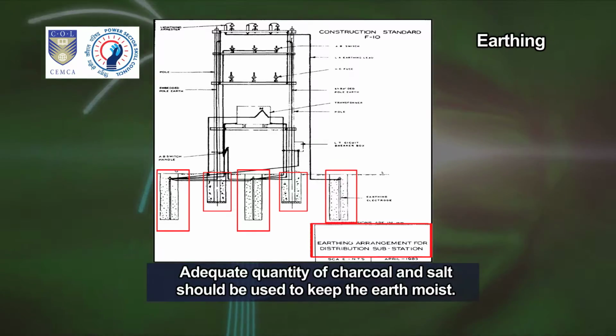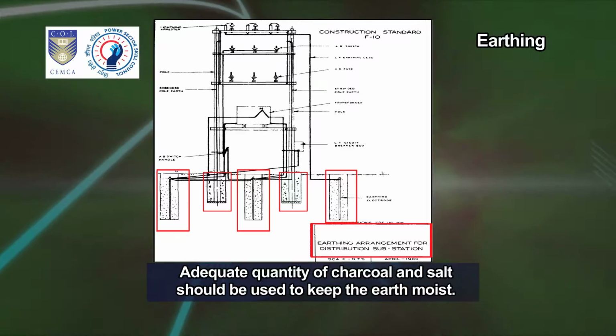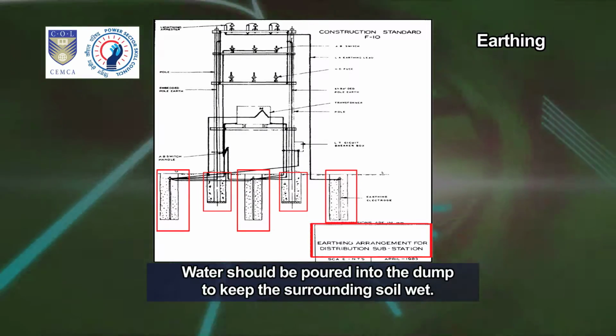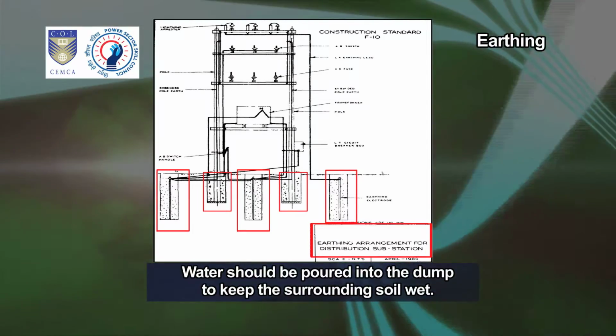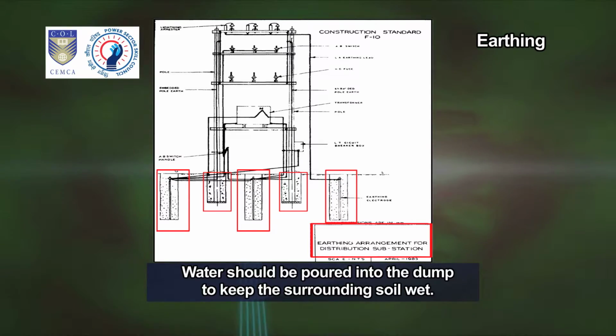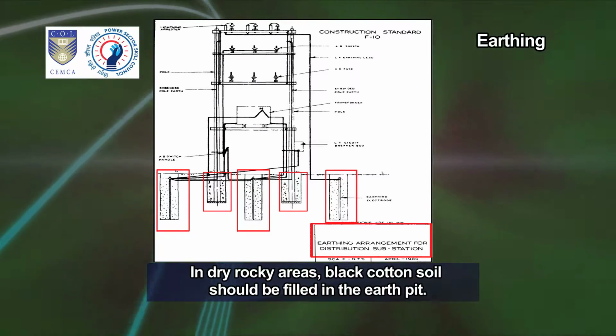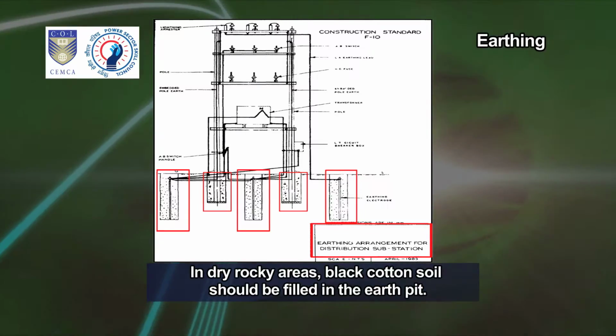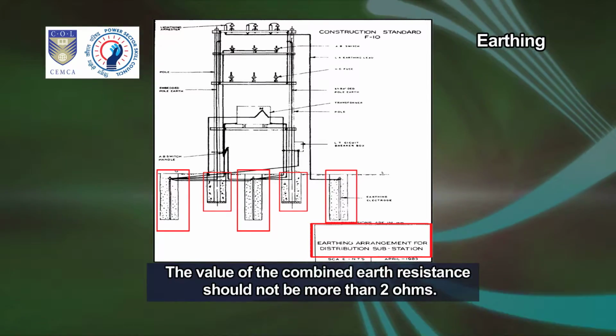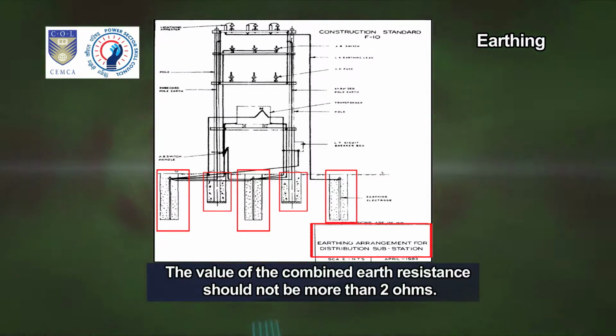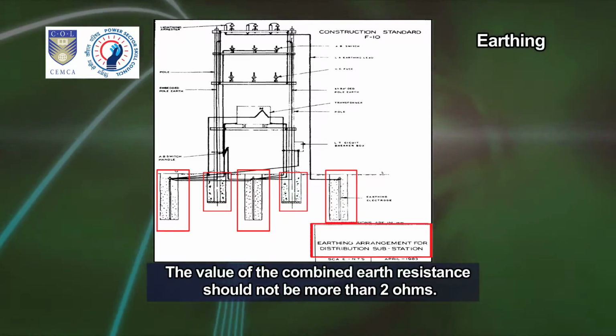Adequate quantity of charcoal and salt should be used to keep the earth moist. Water should be poured into the pit to keep the surrounding soil wet. In dry rocky areas, black cotton soil should be filled in the earth pit. The value of the combined earth resistance should not be more than 2 ohms.